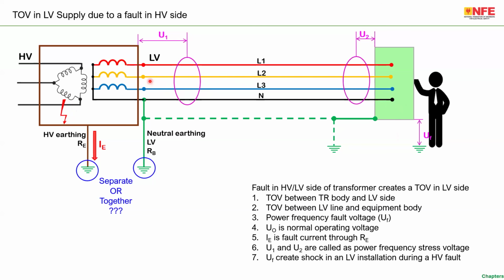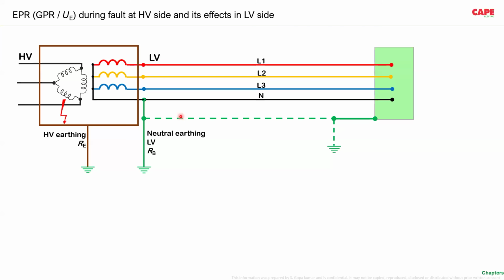All these problems, such as U1, which is the stress voltage on the HT side of the transformer, U2, the stress voltage at the LV side of the transformer, and UF, the fault voltage. Please note that U1 and U2 are stress voltages and UF is the touch voltage or fault voltage in a low voltage installation during a high voltage fault. These three problems must be limited. Let us see what exactly this is. For example, there is a fault here.